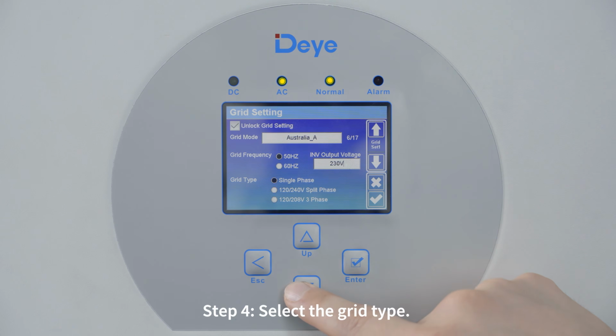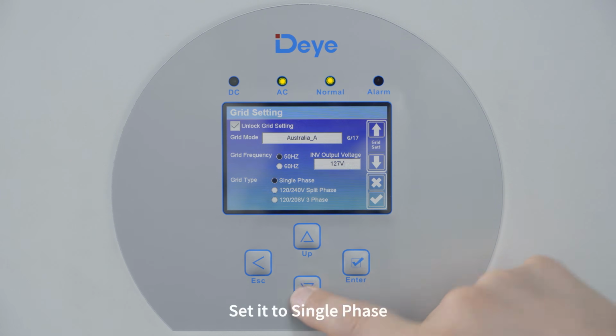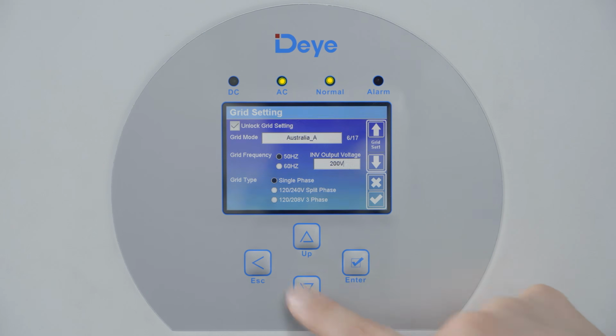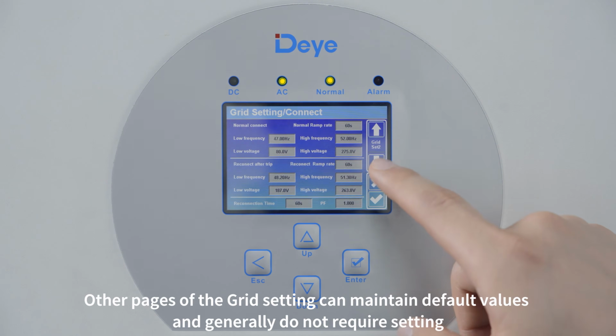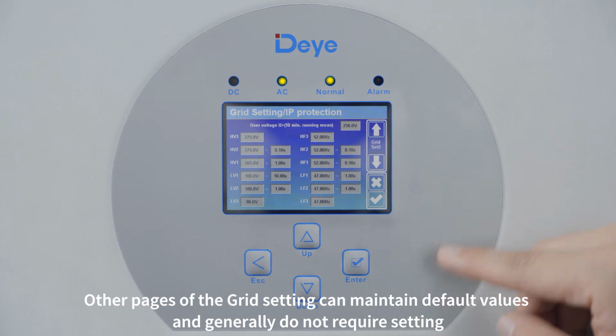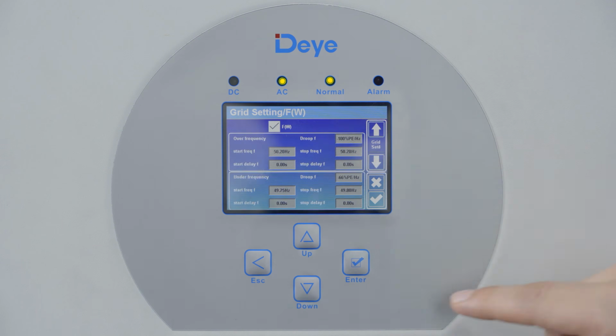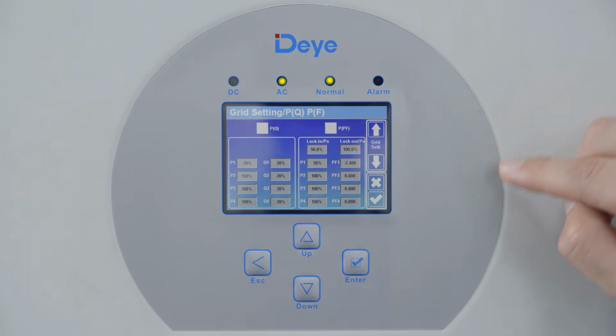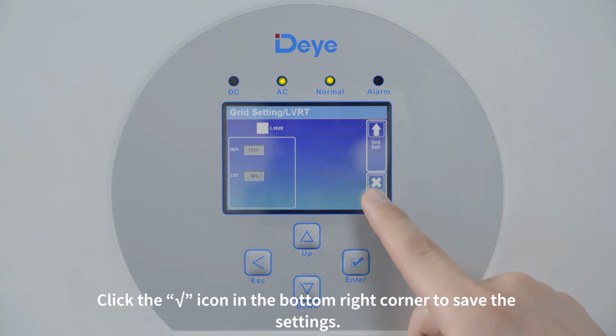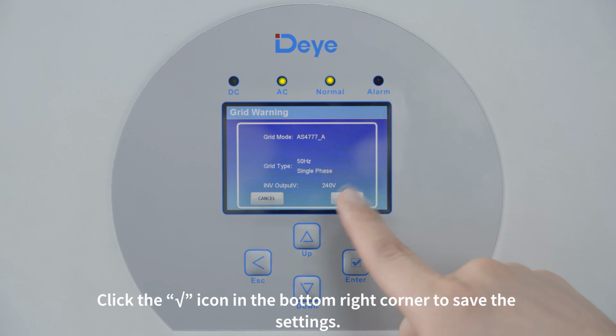Step 4. Select the grid type. Set it to single phase. Other pages of the grid setting can maintain default values and generally do not require setting. Click the square root icon in the bottom right corner to save the settings.